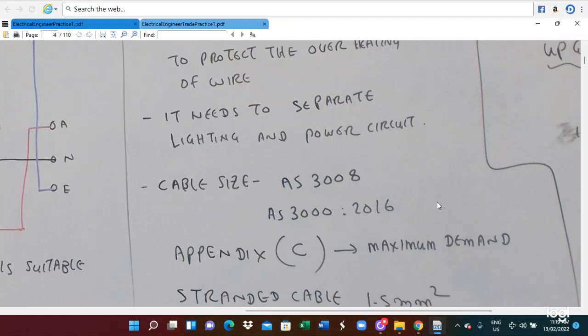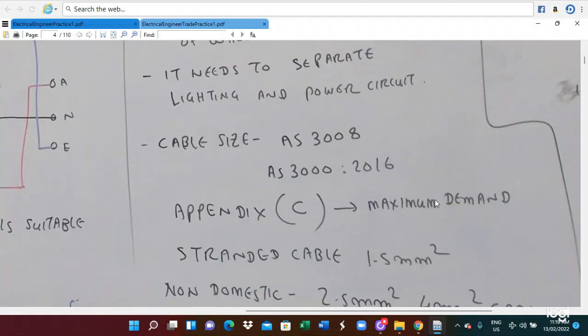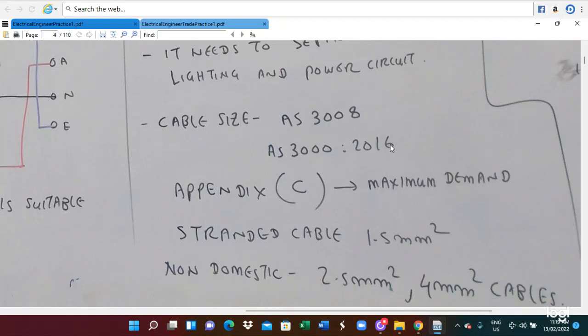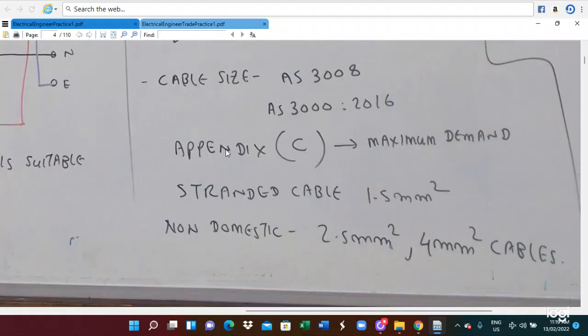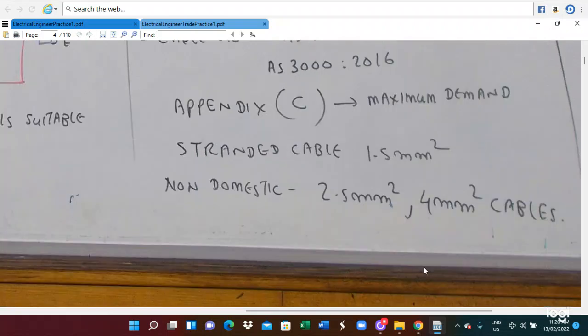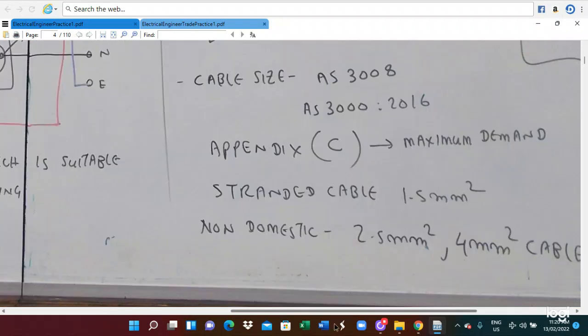And then for cable size, you have to select the cable size by referring to AS/NZS 3008 or AS/NZS 3000:2018, which is used to determine the maximum demand. The stranded cable size is 1.5 millimeter square, and the minimum size in a non-domestic installation can be 2.5 or 4 millimeter square cable. So this is the general information regarding the connections of the electrical lighting system.